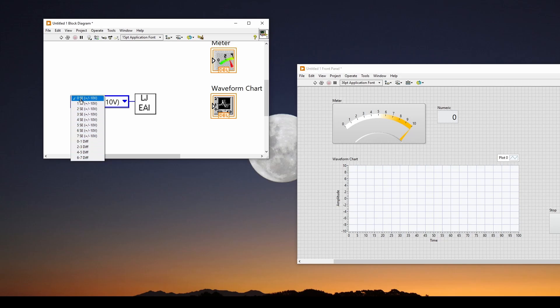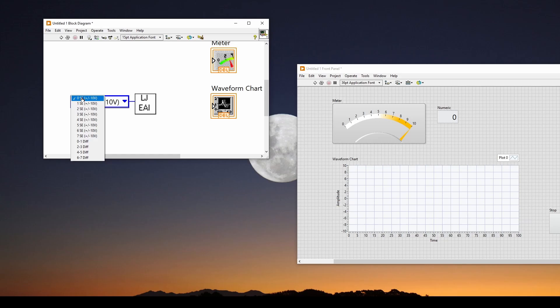You can go down here and use differential. But these are single-ended where one end is ground. And they say, okay, this is limited to plus or minus 10 volts. And we've got the differential if we want to use differential between analog input 0 and 1. But we're going to default it to analog input 0, which is a single-ended.